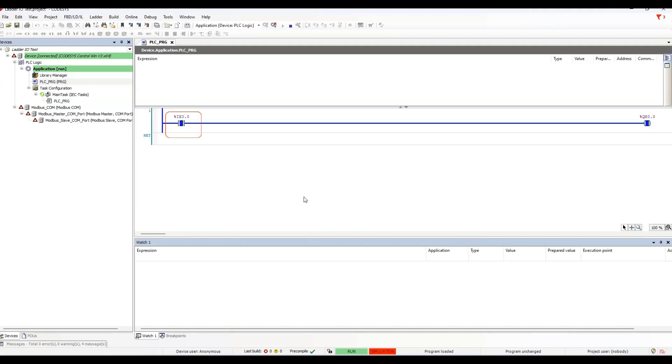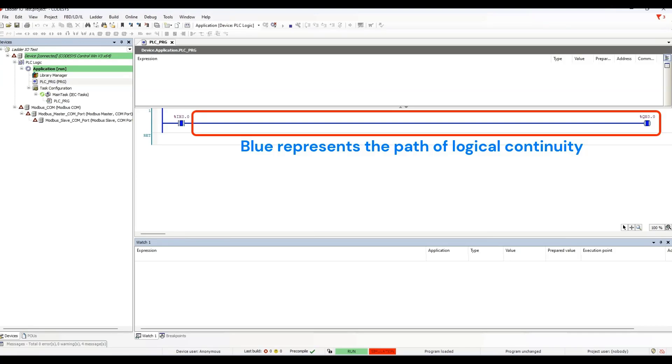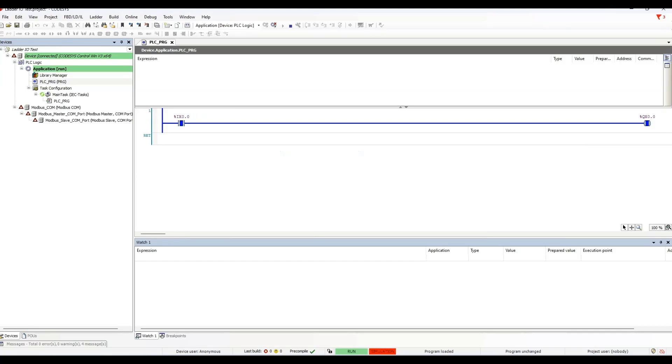Now you see the difference. The contact is now highlighted blue. This indicates the condition for the instruction is true. The horizontal line to the coil is blue, and so is the coil instruction. There is a path of logical continuity to the output instruction. The variable assigned to the coil, QX0.0, is now true in the PLC memory.